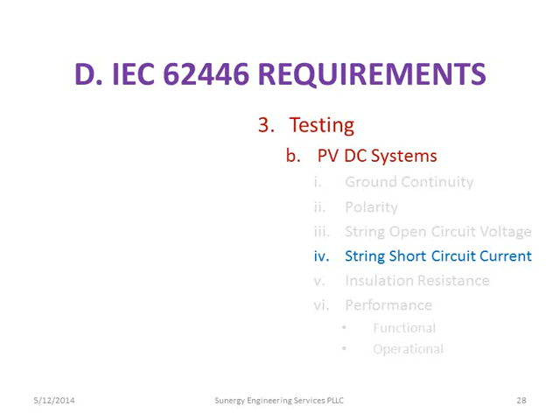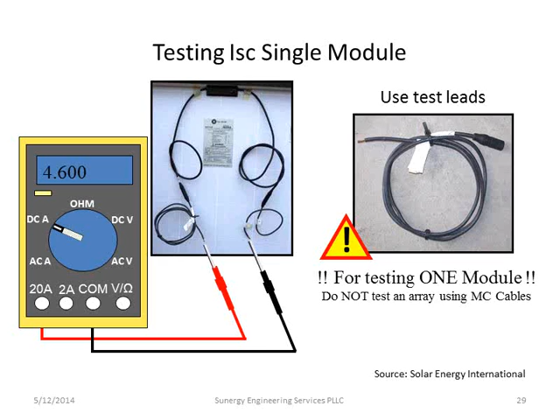if you use these little dummy test leads, because you don't want to do a current measurement with your meter with your probes. When you pull the probes away, you're going to get a little arc, and that little arc is going to carbonize the connector. And once you carbonize that connector, it's probably going to fail over time. I have seen connectors in the field that have totally melted, and I'm guessing that was probably one of the main reasons why that might have happened. Could have been a bad crimp from the factory too, but I'm guessing that someone pulled it apart and went, oops, and put it back together real quick before anybody looked. And there you have it. Over time, that gets worse and worse. The resistance builds up, it gets hotter and hotter, and then under certain conditions it's going to end up melting.